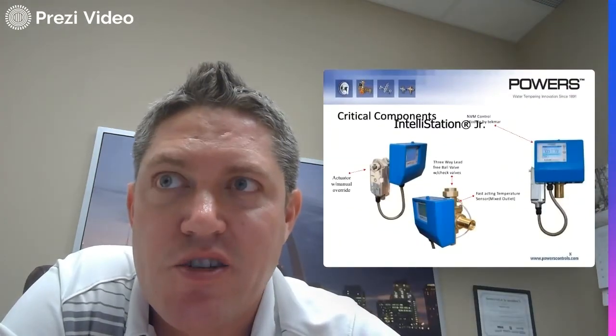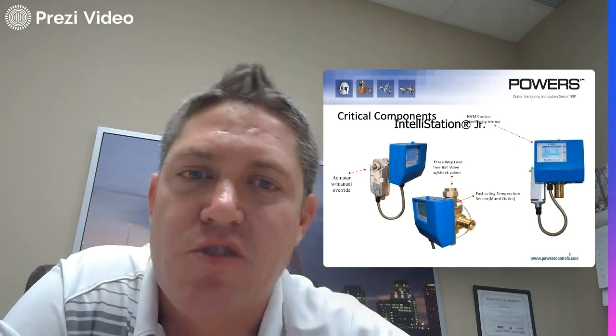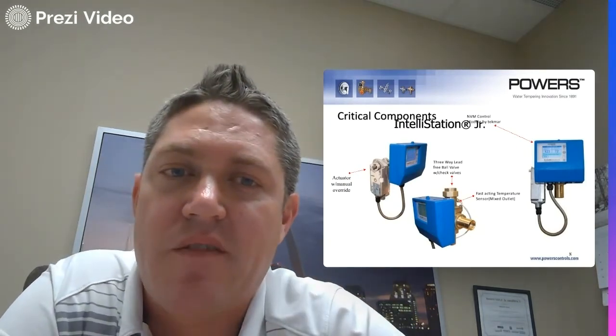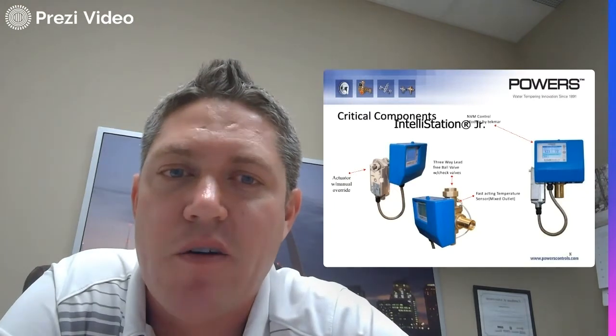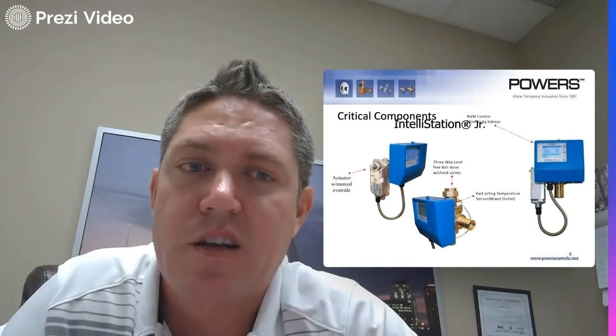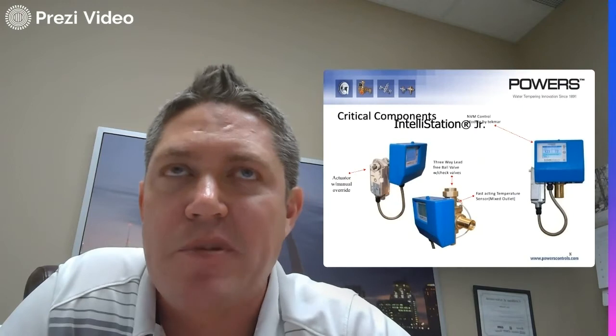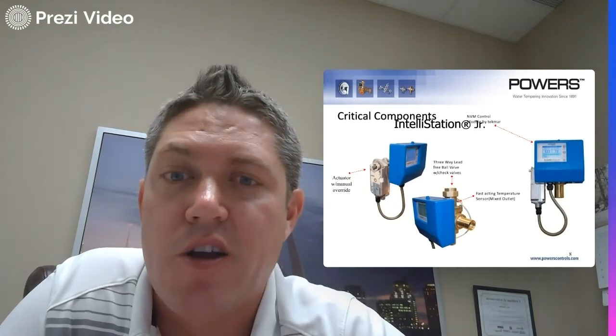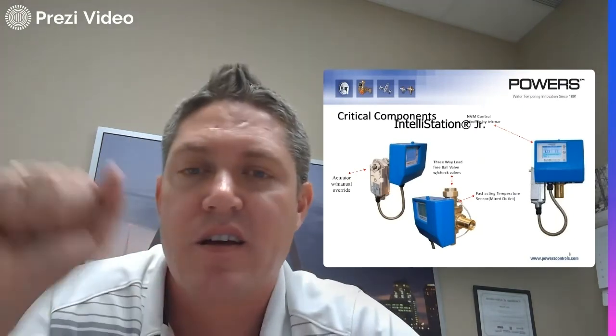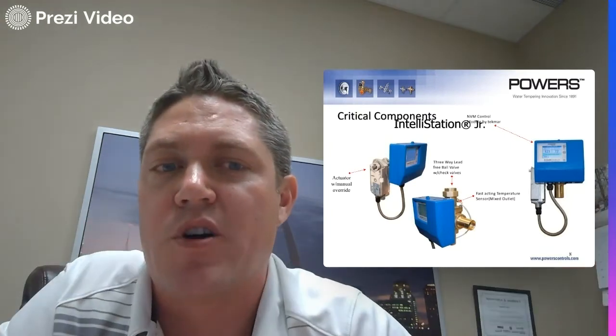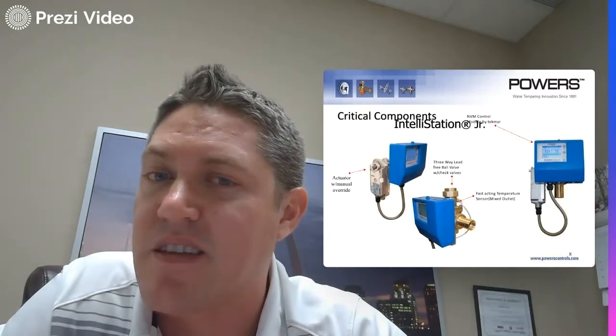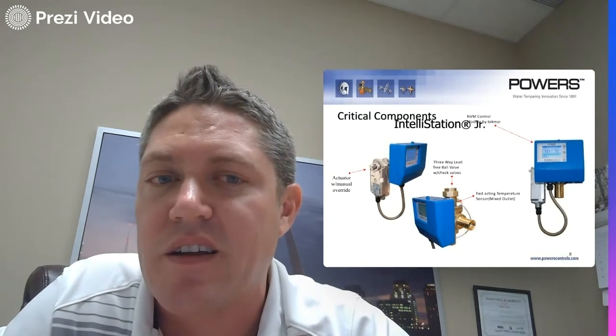Okay, the Intellistation Jr. The Intellistation Jr. was the second generation digital mixing valve that has come out. It's kind of a boiled down version. Instead of having temperature and pressure sensors on your hot and cold inlets, your mixed outlet, and your return, this just has a temperature sensor on the mixed outlet.